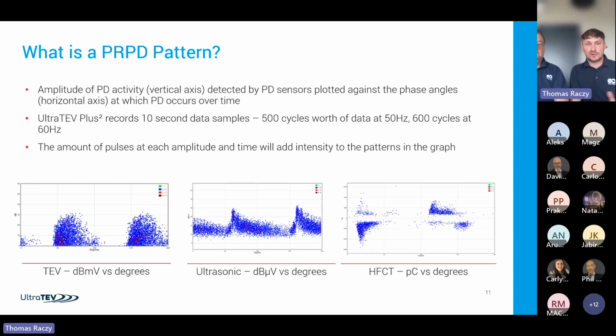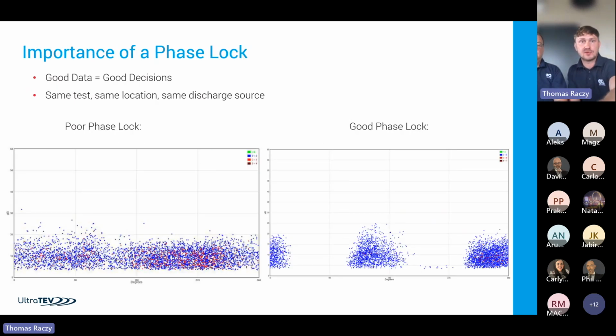You can see representations of those PD pulses as the dots on the screens, and you can clearly see for different sensors there are groups of discharges separated by 180 degrees, whether you look at the TEV, ultrasonic, or HFCT screen on this display. You can also see that some of the dots are of different color, and that is related to the intensity map. So how active those sites of discharge are, or how frequently those pulses occur. If the pulses occur at similar positions or very close to each other, the positions within the cycle, per each cycle, the color will change towards red. That indicates the intensity or repetition rate.